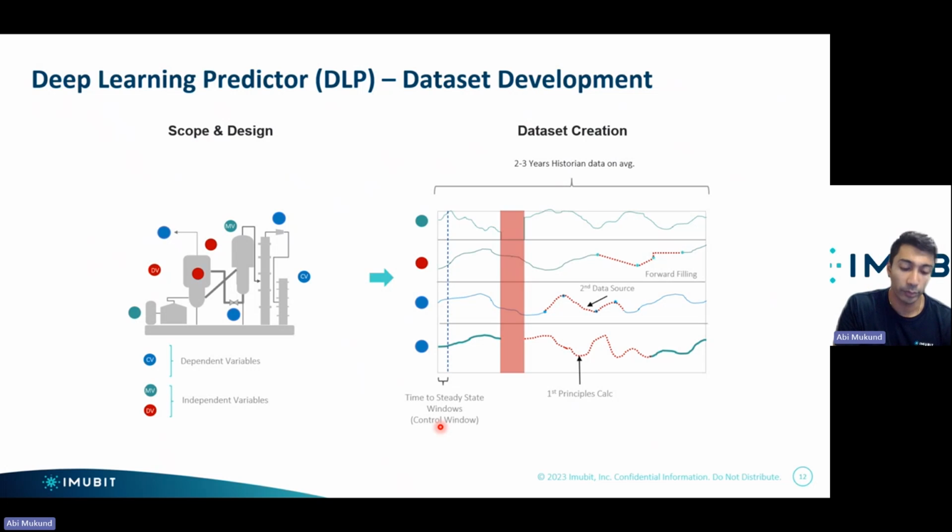Eventually, when we move to train the reinforcement learning model, which is the controller and optimizer, the definitions change to manipulated, disturbance, and control variables. Okay. So when you look at your operating strategy and you define the variables, typically it's about 50 to 100 variables, somewhere in that range. Then you pull years of historical data that's sitting in your historian for those variables. And then it becomes a step of data set cleaning and creation.